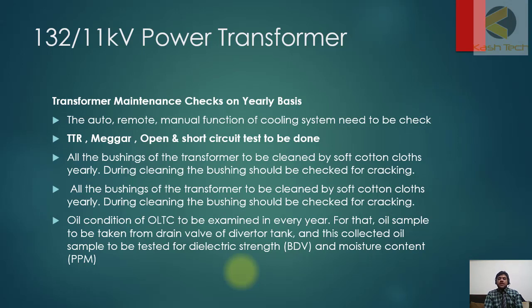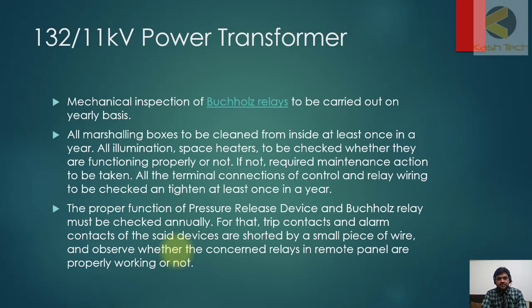The oil condition of the OLTC (on-load tap changer) should be examined yearly. An oil sample is taken from the drain valve of the diverter tank and tested for dielectric strength and moisture content — specifically breakdown voltage (BDV), moisture content in parts per million, and particle count per million. Mechanical inspection of the tap changer is also carried out on a yearly basis.